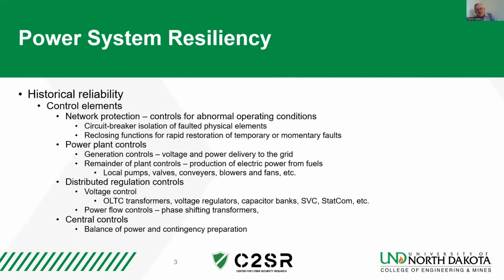In all of this, the primary design objective is the balance of power while keeping a certain amount of resources in reserve for contingencies. And so what this speaks of is the fact that in transmission and distribution and generation and all these levels, not all the resources are used to their fullest extent. We must maintain certain margins in order to allow for events to take place that we were not expecting, and those resources can then be fully utilized without causing overloads and damage to the network condition.